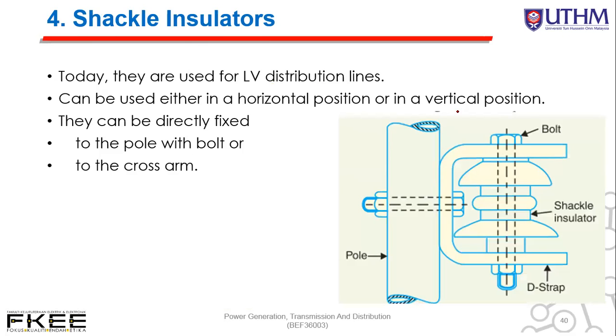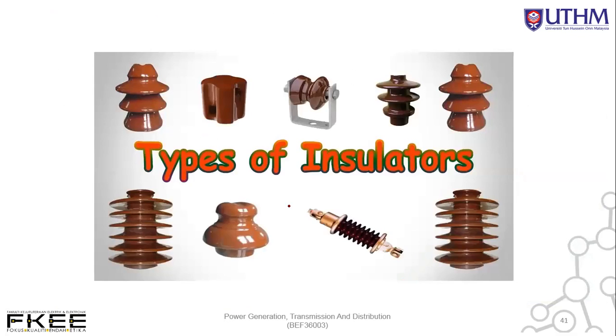Kemudian shackle insulator, they are used for LV, low voltage distribution line, low voltage saja. Can be used either in horizontal position or in vertical position, dan boleh dipasang directly to the pole with bolt or to the cross arm. Ni ada pole, so boleh dia pasang sekali dengan bolt ataupun terus pasang pada pole tersebut. Ini jenis-jenis insulator, gambar-gambar. You can look and see the types of insulator.